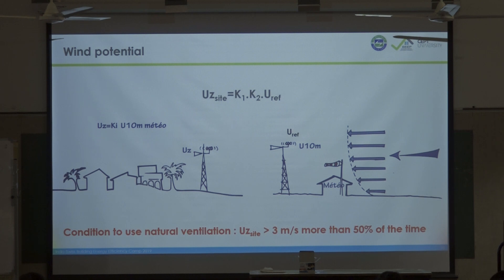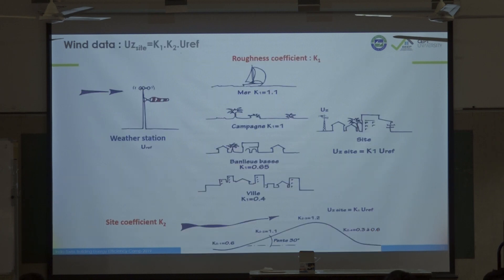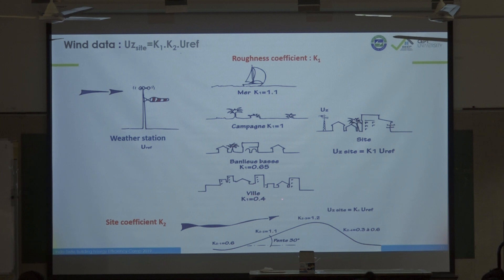k1 is a roughness coefficient — it depends on whether you are at the sea, in a rural area, or in a dense area. In a dense area like Ahmedabad, this coefficient is 0.4, meaning you can get only 40 percent of the wind potential recorded at the airport.